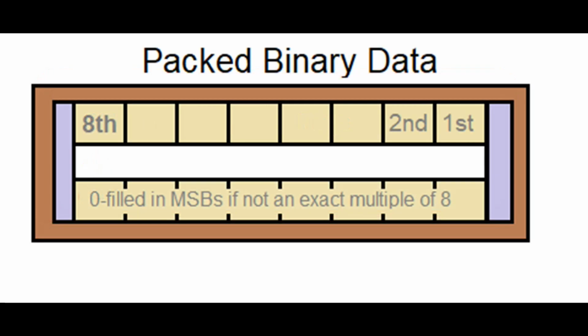When flags are not reported, binary data for 8 points are packed in 1 octet with the lowest index at the right. If the total number of points sent is not an even multiple of 8, the final points are reported in the least significant bits of the final octet, with the most significant bits unused.